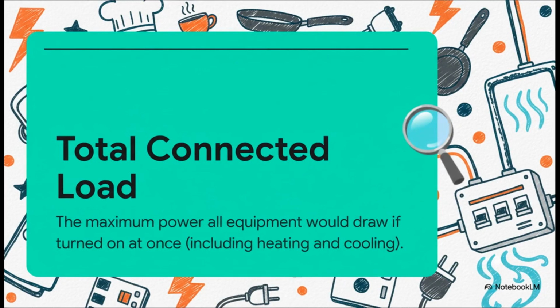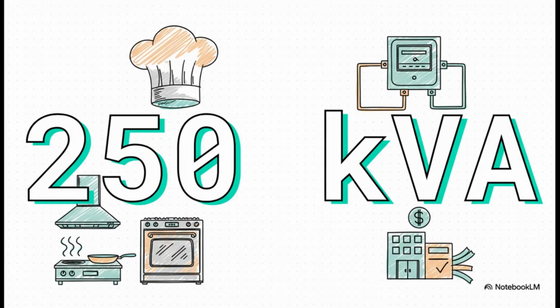Okay, let's get into the core of it then. Table 220.88. How do you actually use it? What's step one? Step one sounds simple, but you have to be thorough. You calculate the total connected load in kVA, and that means everything. Everything, like heating, cooling, cooking, lights, the lot. The whole shebang. Every single electrical load gets added up into one big number. No skipping the walk-in cooler or the HVAC unit. Okay, so total connected load first. Then what? Then you take that total kVA number, find where it fits in the table's ranges, and this is crucial. Figure out if you're dealing with an all-electric restaurant or a not all-electric restaurant. That distinction seems pretty important. It's the main distinction in the table.